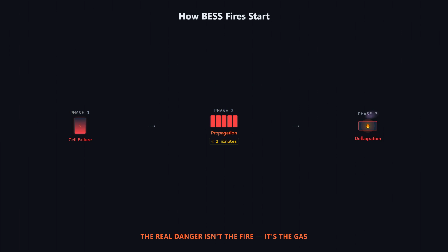A BESS fire typically begins with a single cell failure. Manufacturing defects, overcharging, cooling system leaks, or physical damage can trigger thermal runaway. The same chain reaction we see in EV fires, but at a vastly different scale. One cell overheats, the heat propagates to adjacent cells, and within 2 minutes the entire module can be involved. But the real danger isn't the fire itself, it's the gases. A failing lithium ion cell vents flammable electrolyte vapor, a mix of hydrogen, methane, ethylene, and carbon monoxide. In a sealed container, these gases accumulate. If the concentration reaches the lower flammable limit and finds an ignition source, you get a deflagration, an explosion.